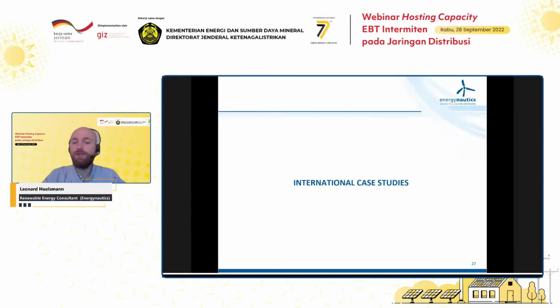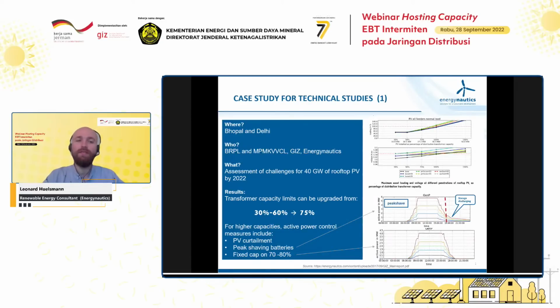I want to share a few case studies from internationally, and I'll try to go quickly through this. This is a study we did in India, where we looked at various distribution feeders and checked what the true technical limits are. This resulted in increasing the regulation, where before PV penetration was limited to 30 to 60% in terms of transformer capacity limits, and this was then lifted and increased.